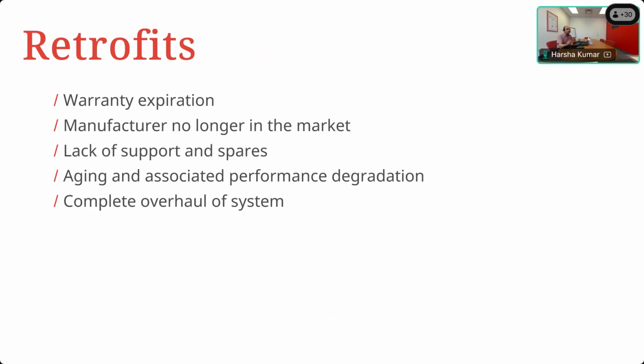Now, when it comes to inverter technology, that degradation of insulation was not as big a deal for transformer-based inverters, because the transformer within the machine provided an inherent degree of safety and protection for the device. Unfortunately, that also comes with cost, because transformers are very expensive, as it's material, it's copper. In addition, they tend to be very unwieldy because of the added weight, and they tend to be a little less efficient than transformer-less inverters. But the biggest advantage was that it was pretty much immune to the aging and degradation of the insulation. That is not so when it comes to transformer-less inverters.